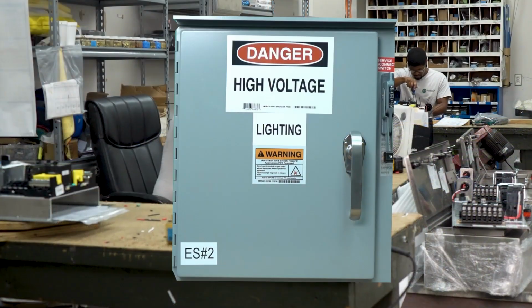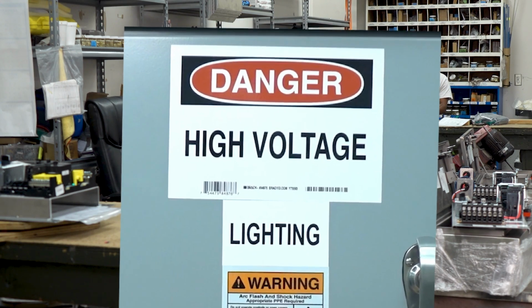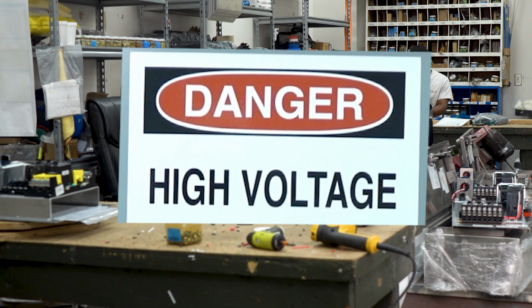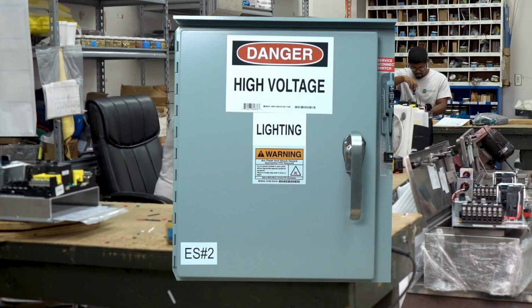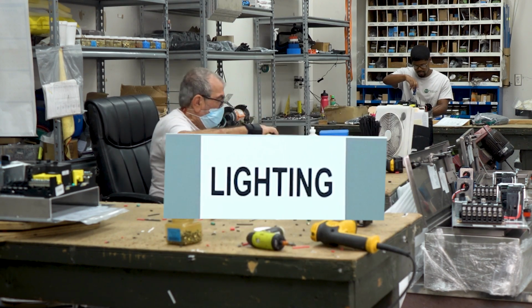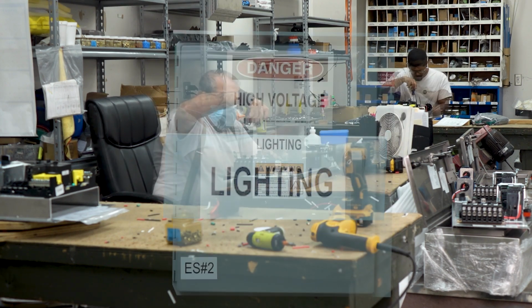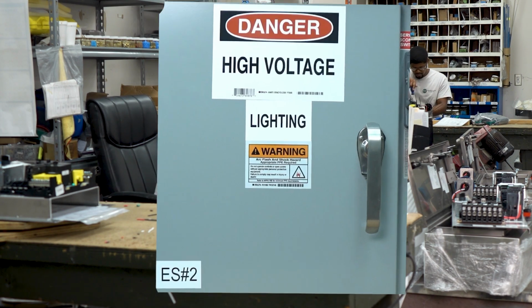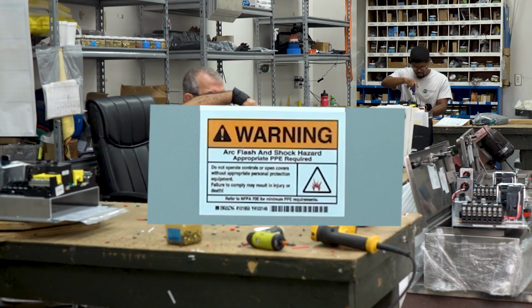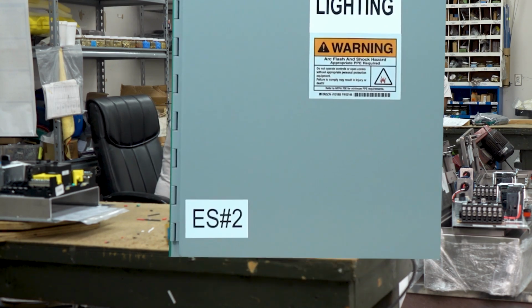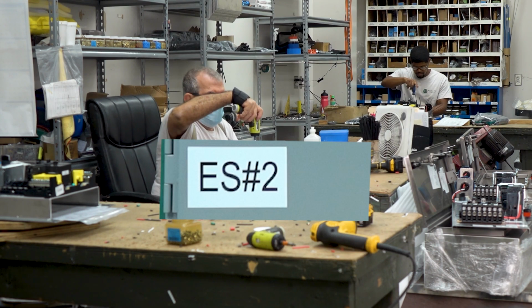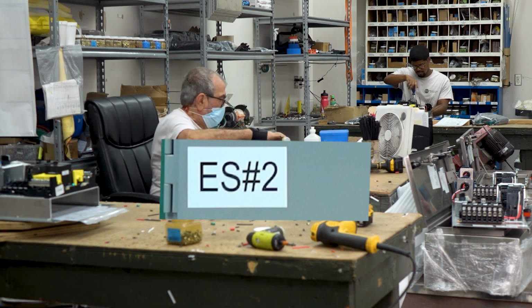All service enclosures must have an OSHA-compliant label on the front door of the service enclosure, showing the words "Danger, High Voltage." The enclosure must also have a label indicating the load served, for example, lighting or signals. The enclosure exterior door must display an arc flash warning label, per the National Electrical Code. Finally, there must be a label with the unique service ID, which matches that shown on the electrical service data chart in the plans.